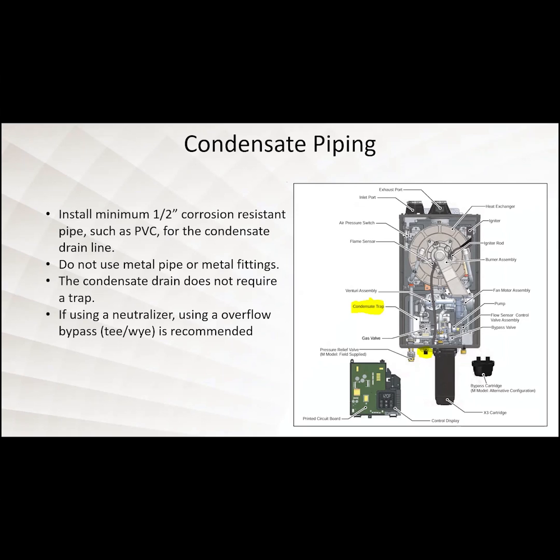With that condensate trap that's built into that unit, you do not need to add a condensate trap on the outside of that unit. So whatever piping you're using and running it down to a floor drain or to a condensate pump, make sure you have plenty of grade going down there. If you are going into a P-trap, if you are going into a floor drain, please do not stick that all the way down inside of the drain to where you're down to the bottom of the P-trap, because it will lock that system up and you'll get condensate backing up into the heat exchanger. Same thing with the condensate pump. Make sure that tube that's going in there isn't down into the water that's inside of the pump. It'll cause that same thing.